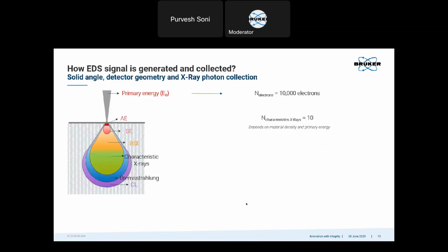Now let's see how many photons are collected within the EDS detector. Previously we had a number of 6,000. Let's round it off to 10,000, just for simplicity. The number of characteristic X-rays generated for 10,000 electrons is 10. This is just a rule of thumb, and it depends completely on the material density and also the primary electron beam energy. So we'll have 10 X-ray photons for every 10,000 electrons.